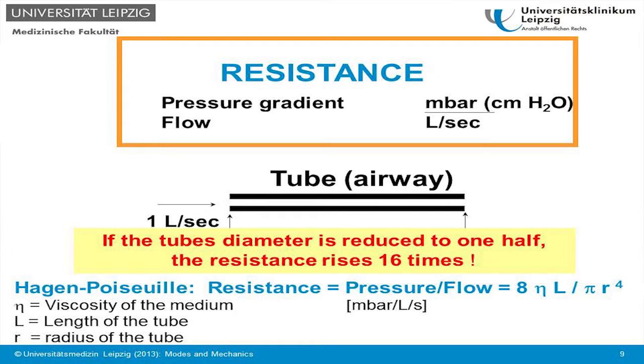The other basic data of the lung we need is the resistance. The resistance is the pressure gradient needed to generate a certain flow. This is symbolized by the tube. We have a pressure of 20 here, for example, and 0 here, and the air goes through the tube, and the flow you get is determined by the Hagen-Poiseuille law, which shows that resistance is pressure by flow. It is a big equation where the most important variable is the radius of the tube, because it goes with the fourth power, which means that if you reduce the tube diameter to 1/2, the resistance will rise 16 times. So the tube diameter is very important, and therefore it's also very important which tube you select to intubate an infant.